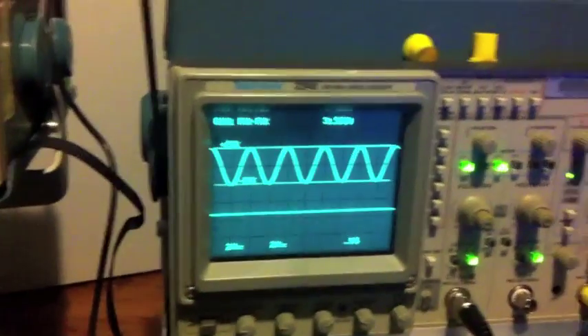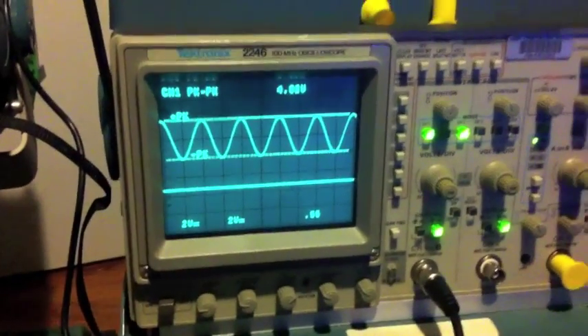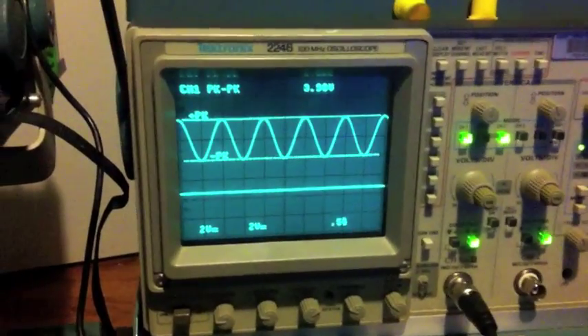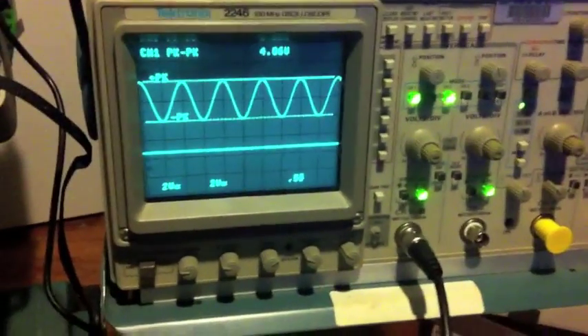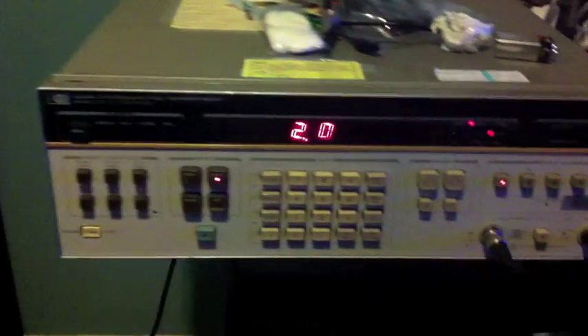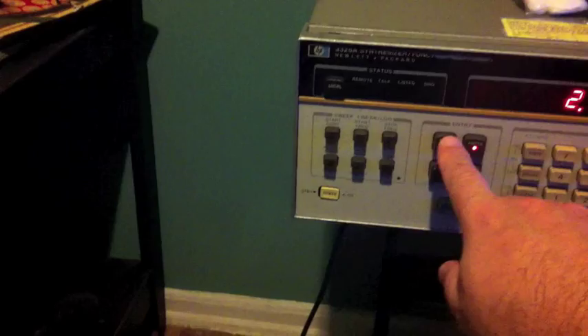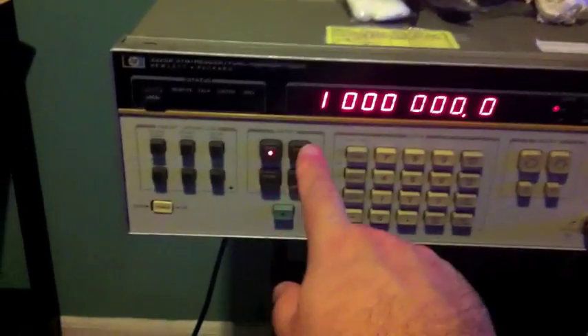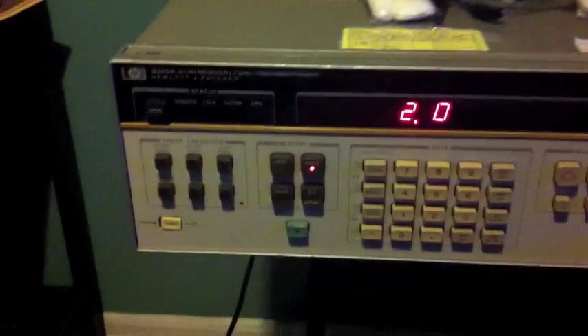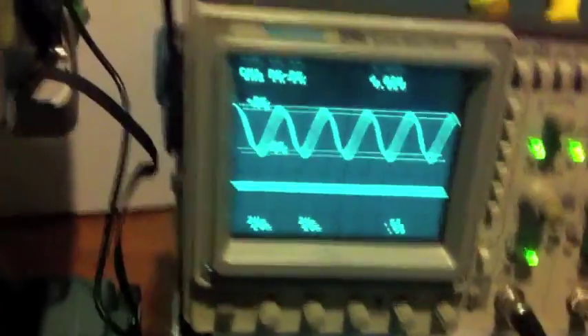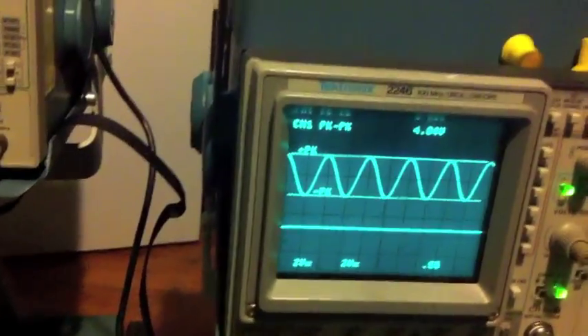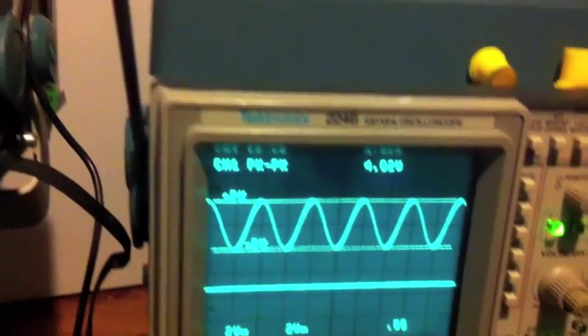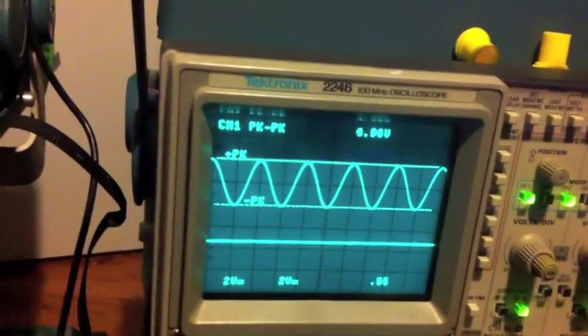I'm now going to do some testing on this Tektronix 2246 oscilloscope using a signal generator to put in a 1 MHz signal with an amplitude of 2 volts. Right now I have it doing peak-to-peak measurement on channel 1 and it is showing 4 volts.